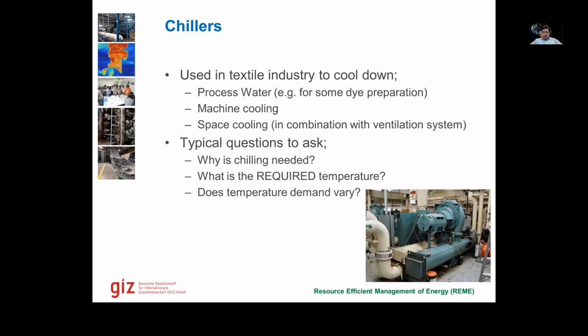Then we come to chillers, which we control pretty much the same way as we control pumps or compressed air systems. The medium is just different for this equipment; the way of operation is the same. We do need to do the sequencing, and we need to match these with the demand side requirement.